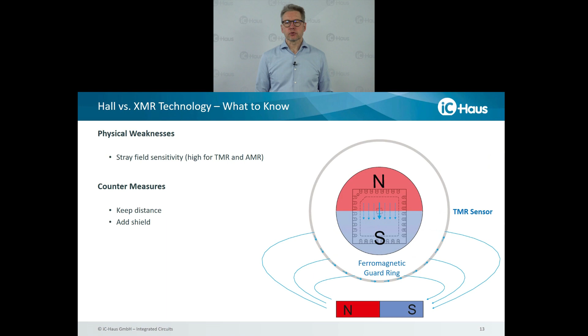The other alternative would be to add a shield. This can easily be done by adding a ferromagnetic guard ring, avoiding the intrusion of the external stray field.